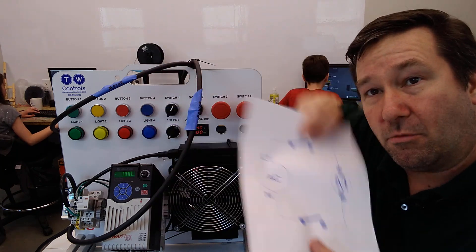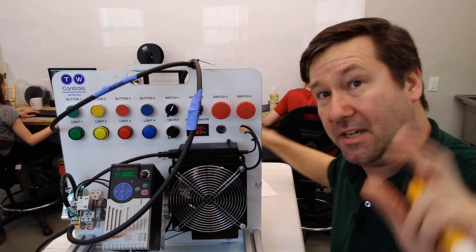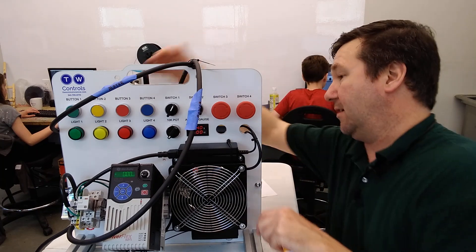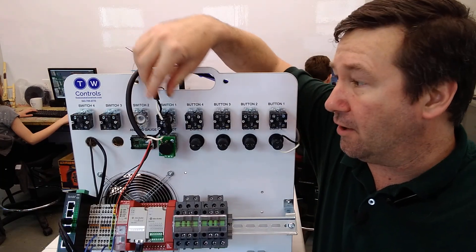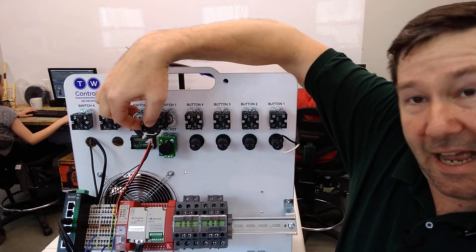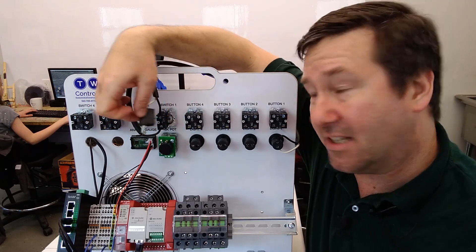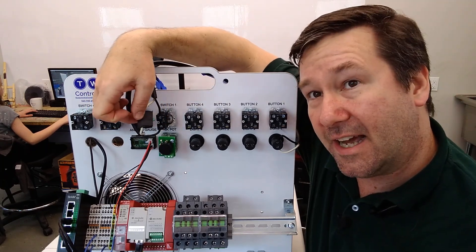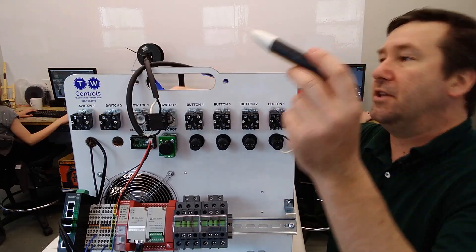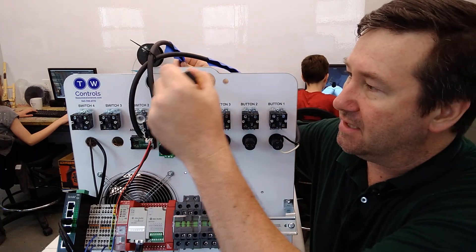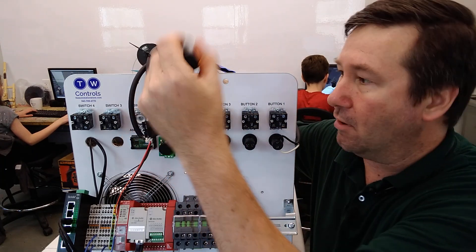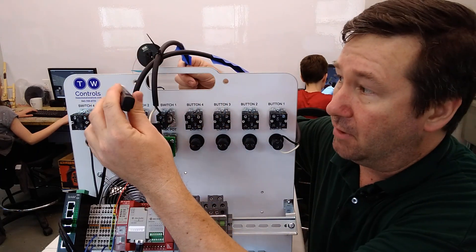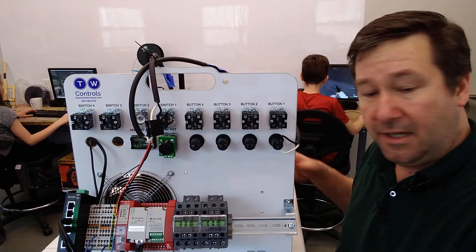Let's go ahead and flip this trainer around so we can see what I've done to make it break. So here is our power wire, and I've kind of simulated the exact break that they had is that the neutral contact was loose. So when you check for power, which was this one, you had power. When you check the one going on the motor, you'll have power going down there.